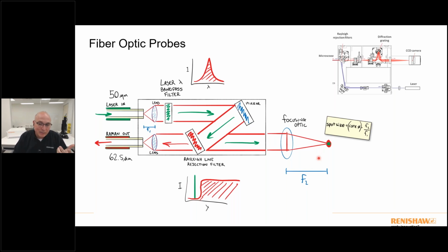And then oftentimes what you'll see is that the collection fiber is a little bit bigger than your excitation fiber, so that you're assured of collecting the full excitation volume coming back into the instrument. So that's generally how fiber optic probes are designed. And this is pretty common. You're going to see this in all sorts of different types of fibers or fiber optic probes.